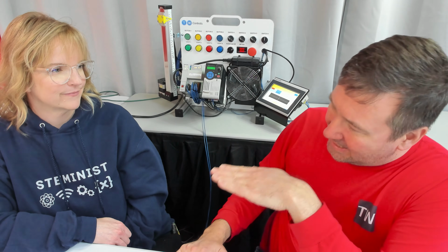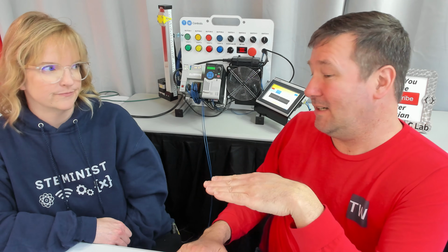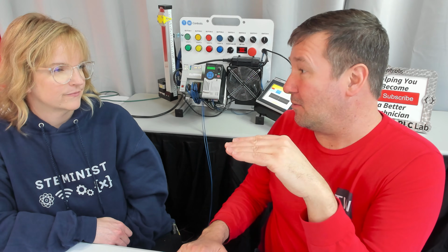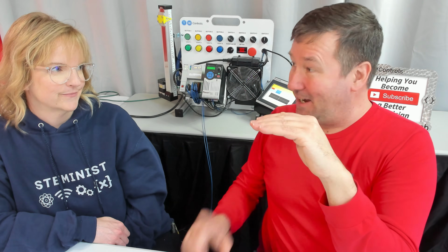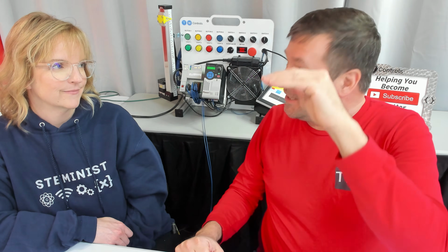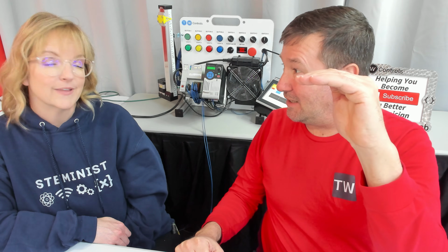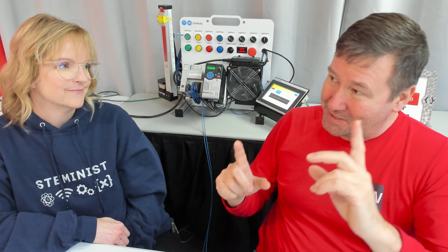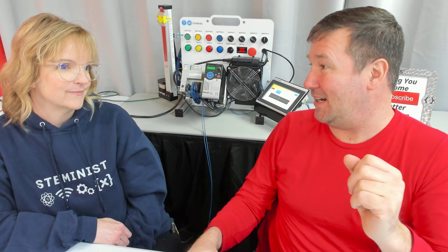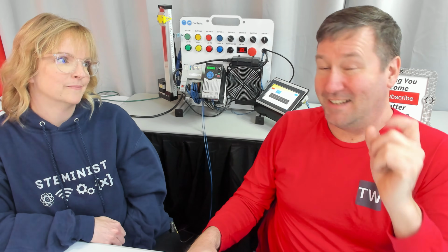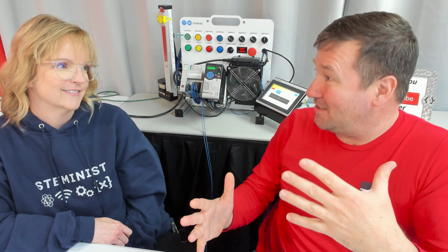So Amber, if our tank is empty, should our pump be running? No. At 2.4 feet, should our pump be running? No. At 2.6 feet, should our pump be running? No. That's right, because we haven't got to our start level yet. So at 4.9 feet, should our pump be running? No. We hit 5.1, should our pump be running? Yes. Okay, now we go back down to 4.9, should our pump be running? Yes. What's the difference between the first time we hit 4.9 and the second time we were at 4.9? The second time the pump was already running. And that is the key thing to understand about how to do this type of logic.